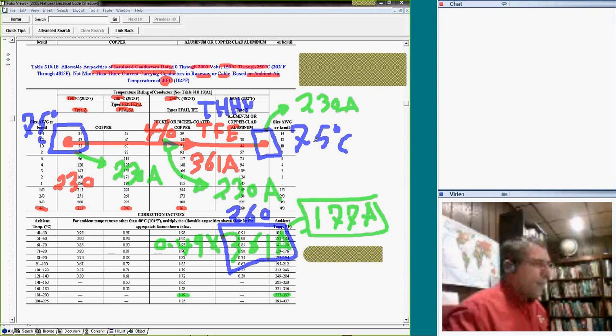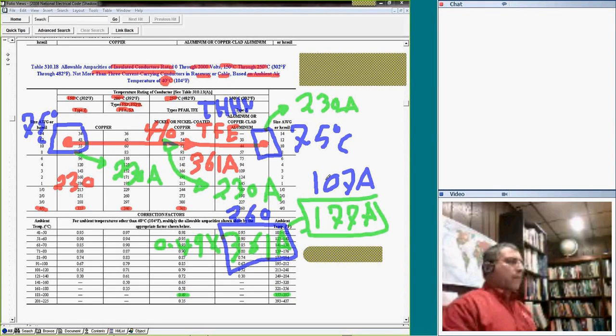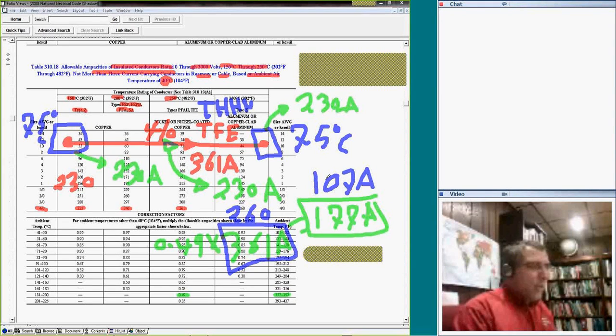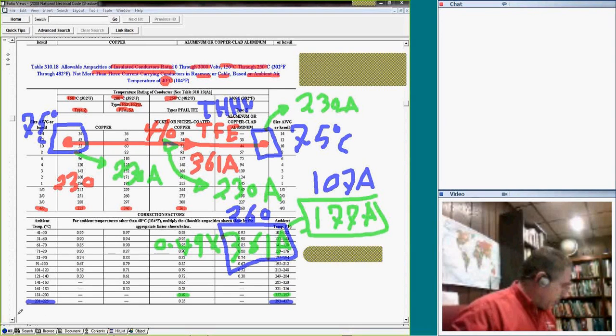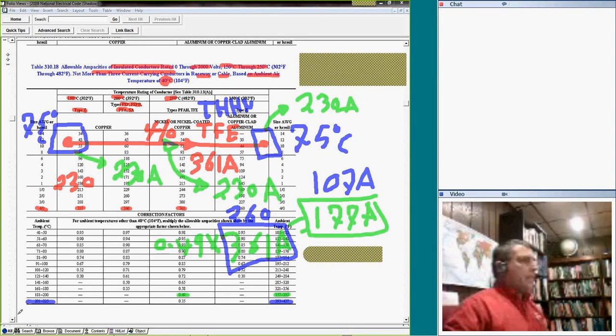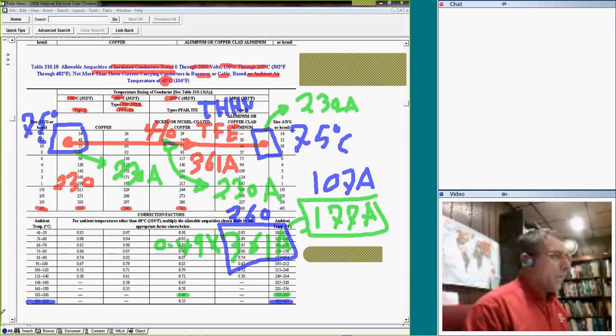You have 5. If you use the THHN, you're going to end up with 107 amps. Look how small an amount of amps you can pull out of this conductor. So I'll give you an idea why we use these conductors. Look at the very high temperature, guys. They can go all the way up to extreme temperature. Unlike the THHN, these are rated for places in boilers and places where the ambient temperature can become really hot.